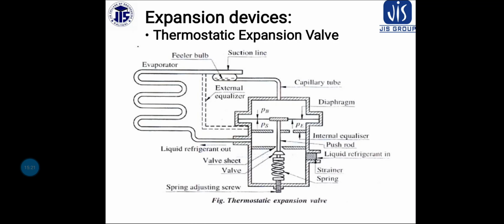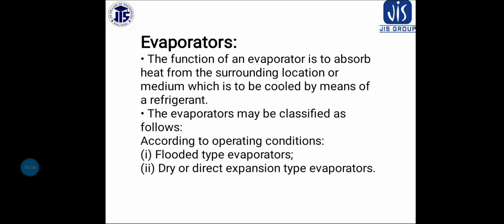Most thermostatic expansion valves are set for 5 degree centigrade of superheat and are usually rated in tons of refrigeration. So this is all about the expansion device.